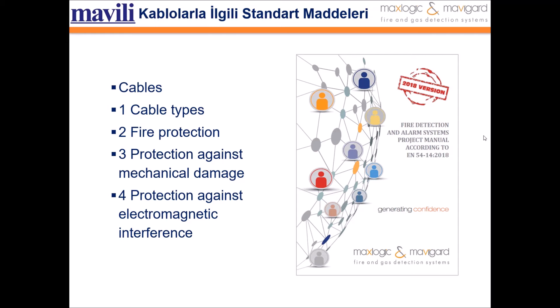Standard fire resistant cable must meet the PH30 classification when tested according to EN standards, and also a 30-minute survival time when tested according to EN standards.